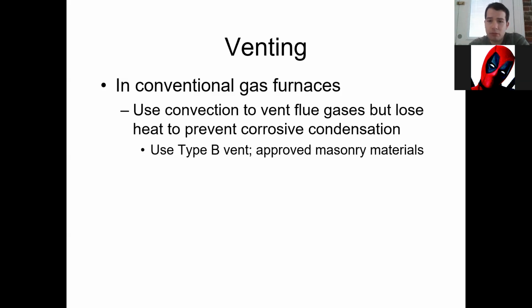So the big thing with the old style with the metal flue piping, and this is something that I've told you guys about before, you can go to a job where the flue piping is just rusted out. It's gone. It's not there, and you need to replace it. And what's happened is, over time, combustion's taking place, flue gases are going up in that vent, all right?